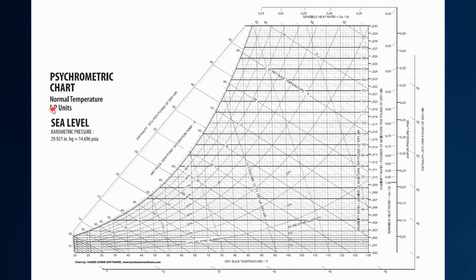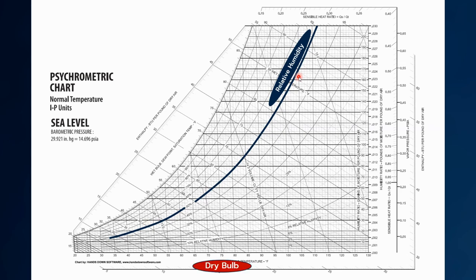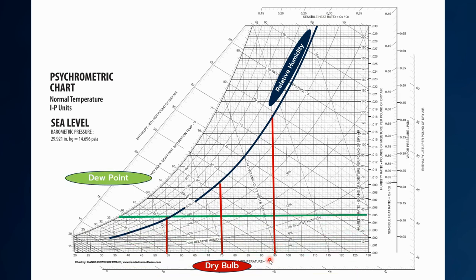This is a psychrometric chart — if you're not very familiar with it, we'll probably do another presentation because there's a lot of information here, but I'm going to make it very simple. We'll plot the relative humidity of 50%, represented by this line we just put on here. Then we'll draw in the three dry bulb lines we have: 55 degrees, 75 degrees, and 95 degrees, and plot the intersection of all this with our dew point lines.